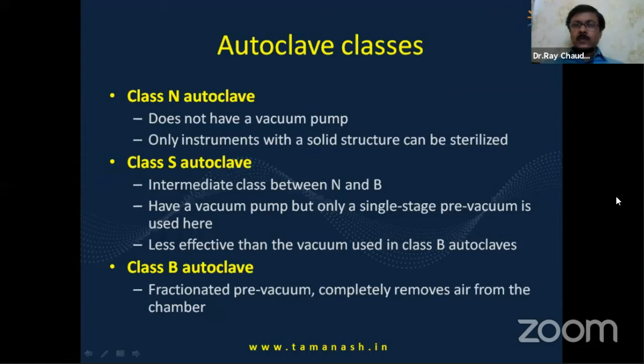The next classification of autoclaves is according to class: class N, or normal autoclave; class S, which is in between N and B; and class B, which is the one that is supposed to be used in ophthalmology or medical setups. These have a pre-vacuum and completely remove air from the chamber. So we will be talking mostly with reference to class B autoclaves only.